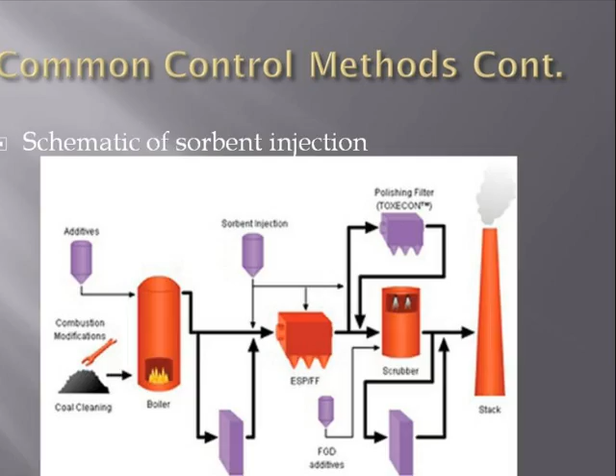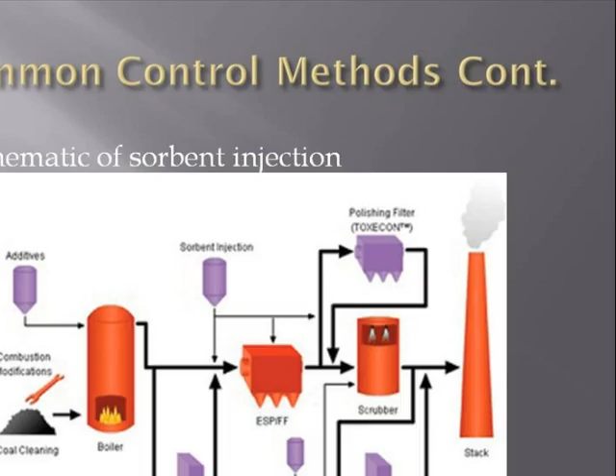Most recently, other methods have been introduced. Sorbent injection is one method to control mercury emissions. Here is a schematic of sorbent injection. It consists of powdered activated carbon, PAC, which absorbs mercury at increased levels and faster rates in comparison to the old system of homogeneous and heterogeneous reactions. However, due to the high temperatures that occur in coal-fired power plants, PACs have been found to be less effective as the levels of mercury absorbance decrease in temperatures exceeding 350 degrees Fahrenheit. Due to further research, it has been found that enhanced PAC, silica-based sorbents, can in fact operate at more elevated temperatures, thereby increasing the level of absorbance of mercury and ultimately decreasing mercury emissions into the environment.